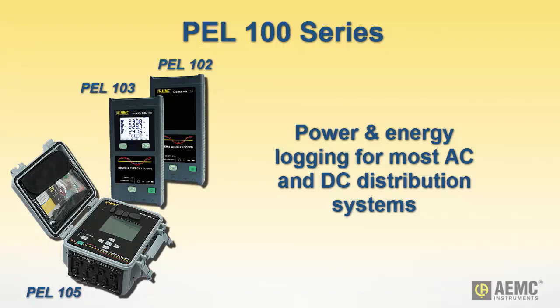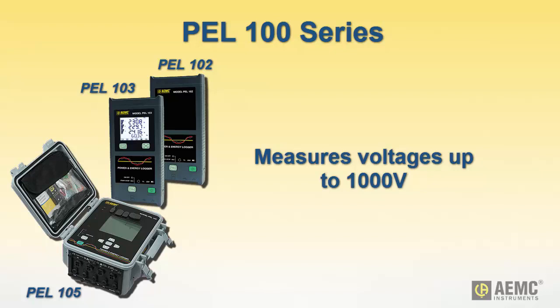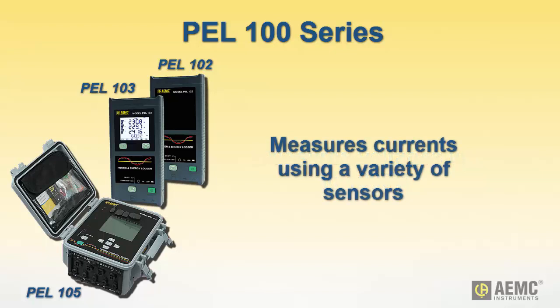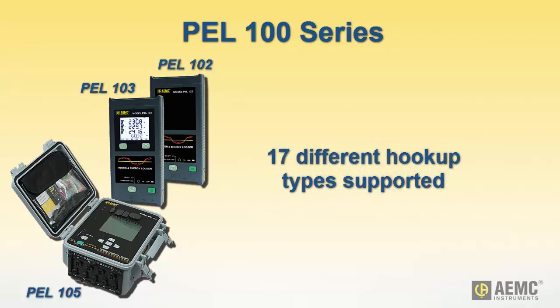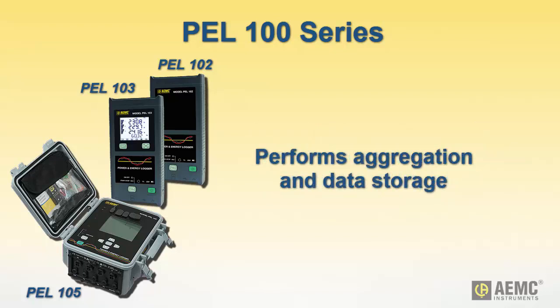For demanding requirements, the Power and Energy Logger PEL series provides all the necessary functions and features for power and energy logging for most 50 Hz, 60 Hz, 400 Hz, and DC distribution systems worldwide. Primary users include contractors performing power system evaluation and monitoring. These instruments measure phase-to-phase, phase-to-neutral, and phase-to-earth voltage up to 1,000 volts, and phase-to-neutral current using a variety of external current sensors. A total of 17 types of electrical hookups are supported. Measurement data is used to calculate numerous values including active, reactive, and apparent power and energy, power factor, harmonics and total harmonic distortion, and others. Quantities can be aggregated from 1 minute to 1 hour and stored on an SD card.